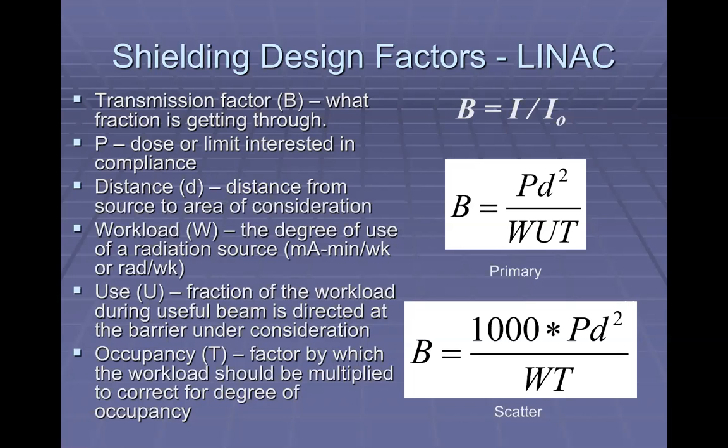It's a drastic difference. We know that these machines aren't on all day, every day. They're on to treat patients and maybe a little bit of QA work. So that's an important piece of the puzzle to know. The use factor. The use factor is different from the workload.